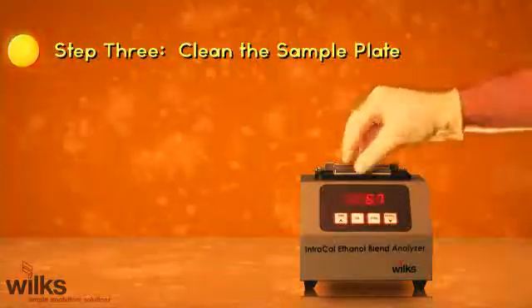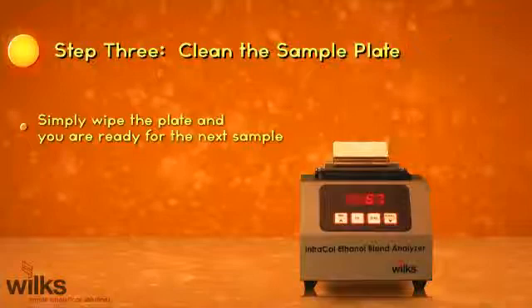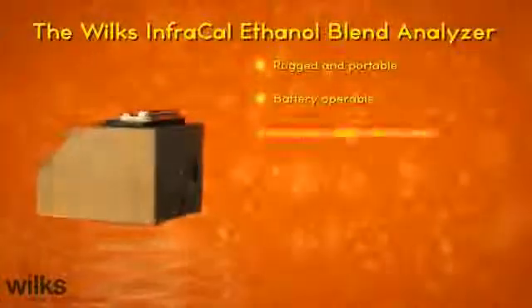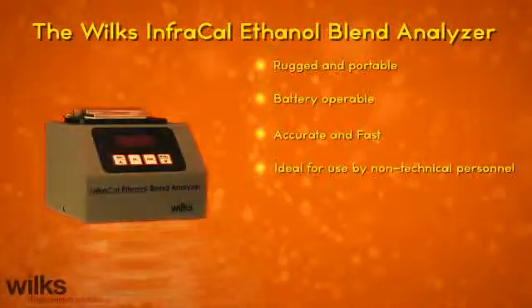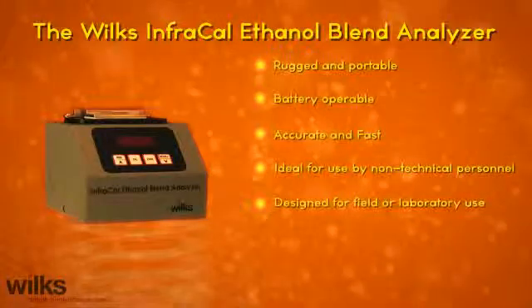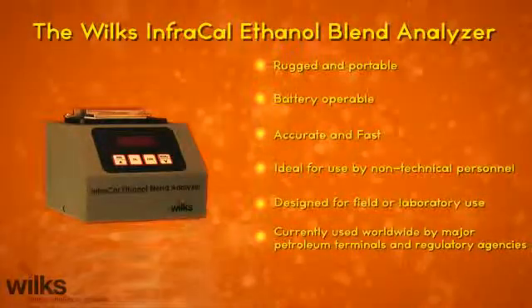Step 3: Clean the sample plate. Simply wipe the plate and you are ready for the next sample. The Wilks InfraCal Ethanol Blend Analyzer is rugged and portable, battery-operable, accurate and fast, ideal for use by non-technical personnel, designed for field or laboratory use, and currently used worldwide by major petroleum terminals and regulatory agencies.